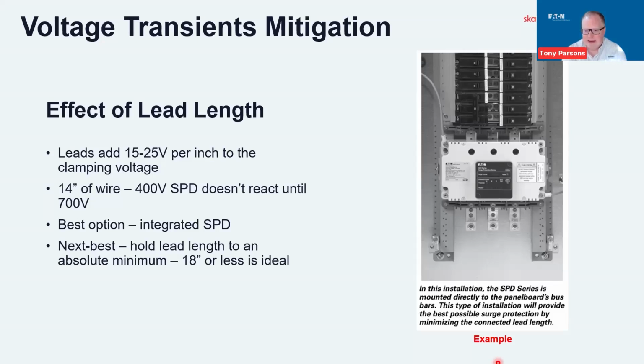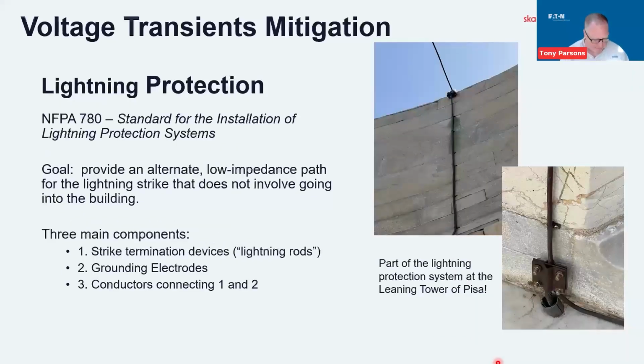Well, the impedance of that lead can reduce the effectiveness of the surge protected devices. The typical recommendation is to keep those leads to 18 inches, or roughly half a meter, or less, which would be the ideal case. As far as lightning protection, again, kind of a different animal altogether. In the U.S. there is a standard, NFPA 780, that deals with design and installation of lightning protection systems. In the IEC world, IEC 62305 has some similar information. The goal with this, again, is to give an alternate path for that lightning to flow.